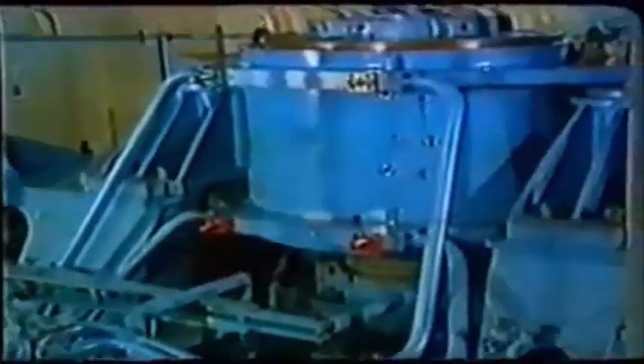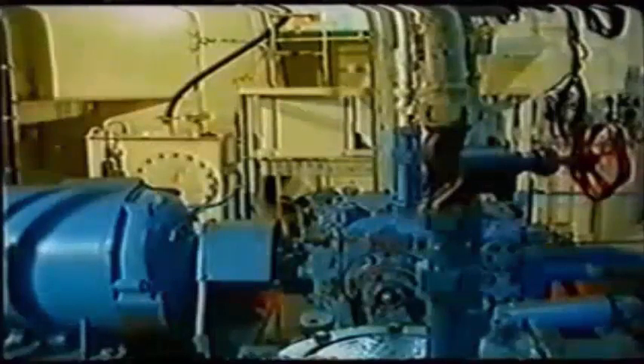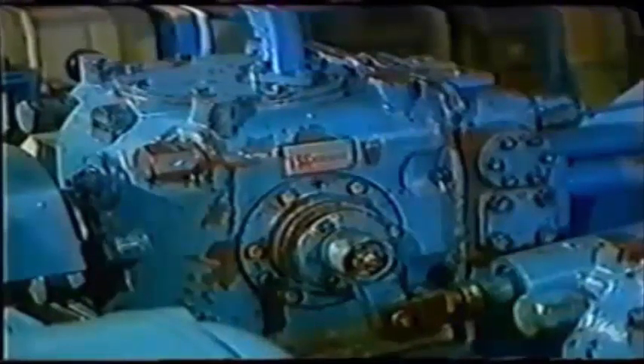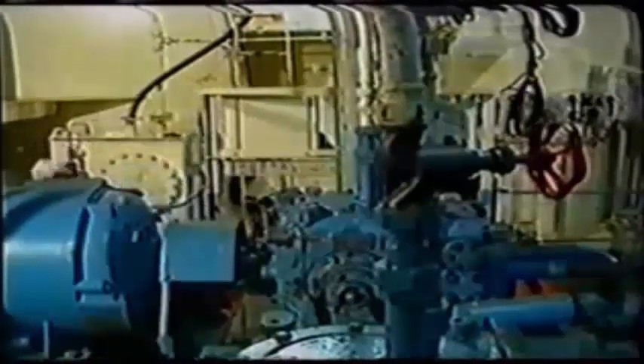The hydraulic fluid in a steering gear system is not subjected to undue stress. Hence, a good quality hydraulic oil of the correct viscosity will suffice. It is important that the viscosity requirements of the hydraulic pump manufacturer are observed, and that the oil is kept clean and free from moisture. So long as the system is leak-free, there will be little make-up required, but it's essential that frequent and regular checks are made on the reservoir level indicator.